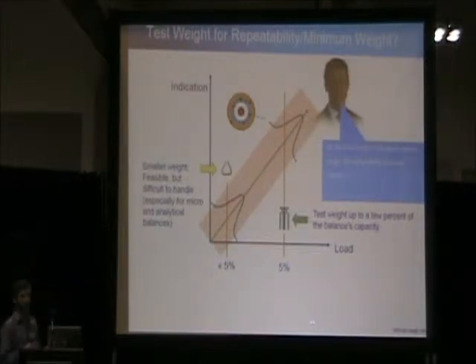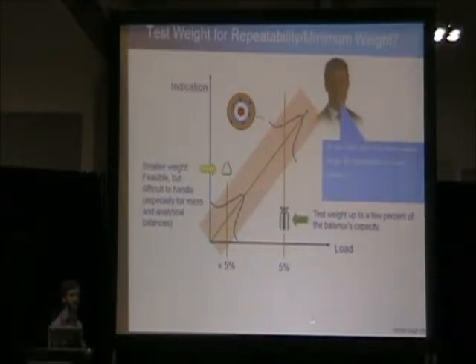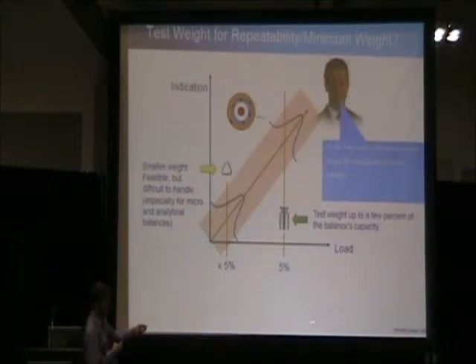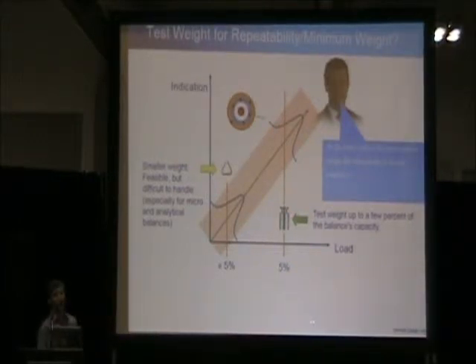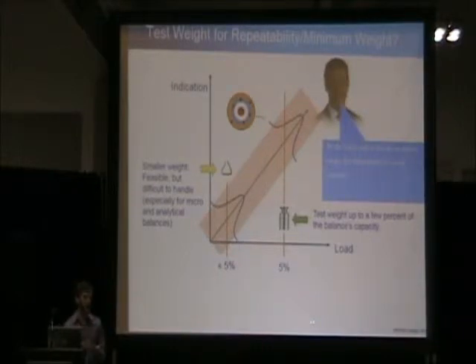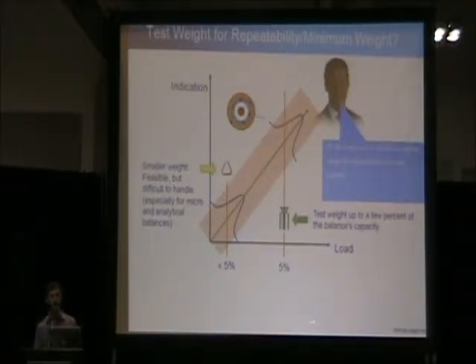The reason why we recommend to use a test weight closer to 5% and not way below 5% is that it's much easier to handle a cylindrical mass like this than it is to handle a wire weight. Those steel masses also stay in calibration much longer than a wire weight. What that means is that it's going to be easier for the end user to handle when performing routine testing, and it's not going to go out of calibration as frequently.